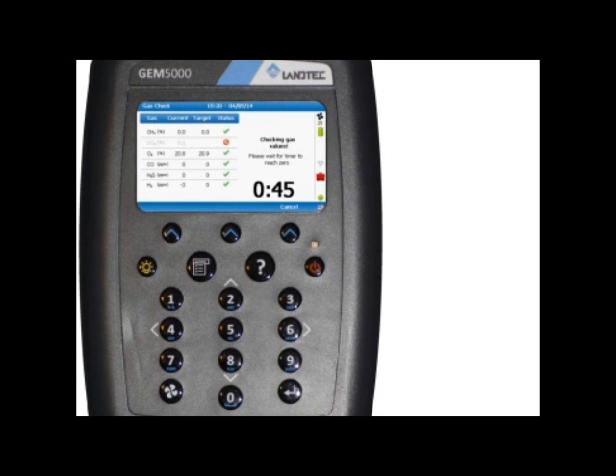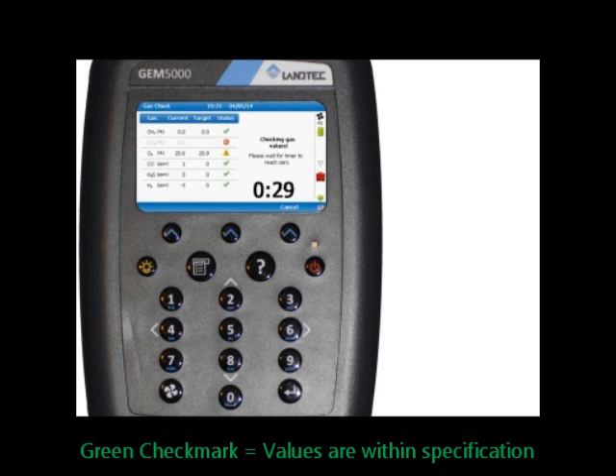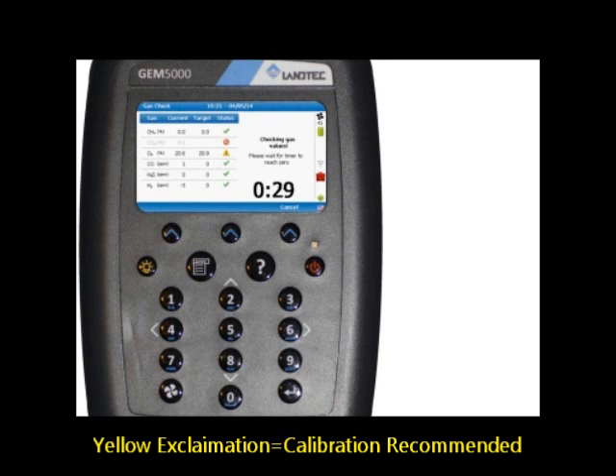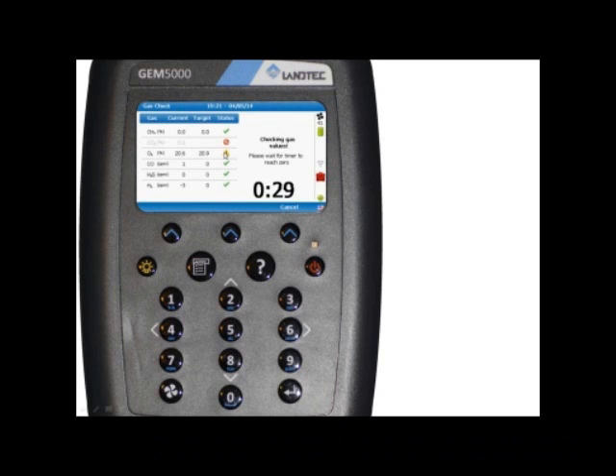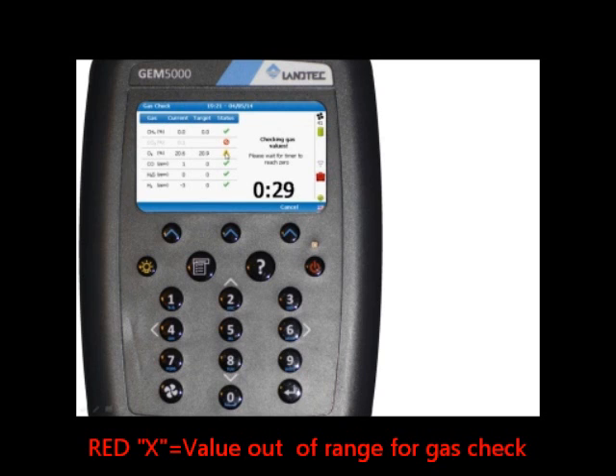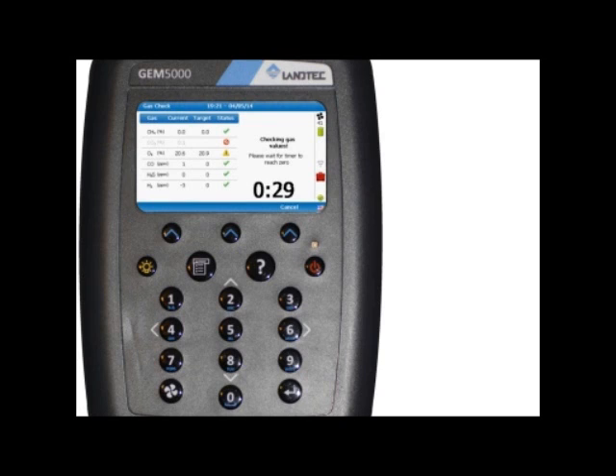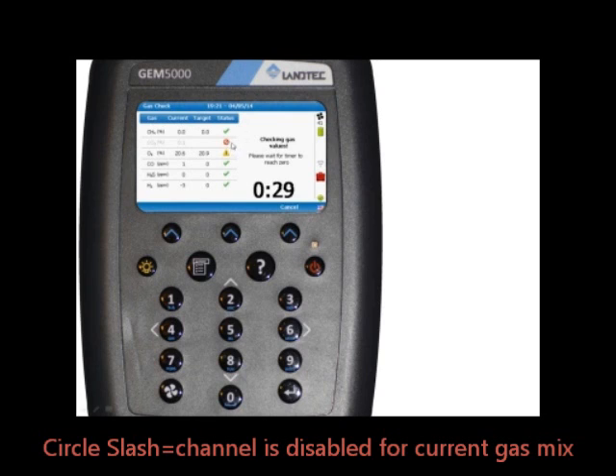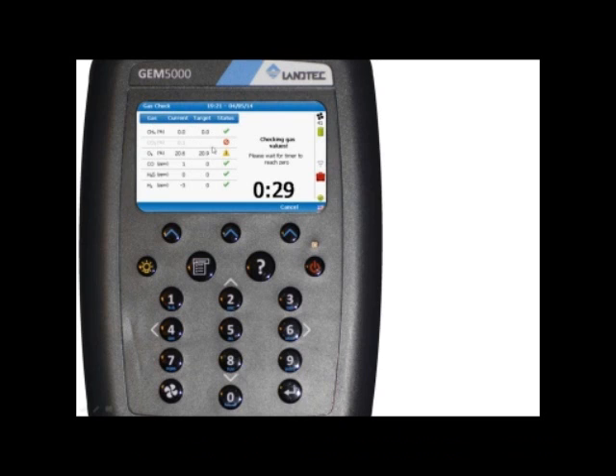Note that during this stabilization period, the current column is going to show the live readings. The target column shows the values we're calibrating to, and under the status column you may see several symbols that might be changing during this period. A green check mark means that the current value is within specification. A yellow exclamation symbol means that the values are close to the target gas, but a calibration is really recommended at this point. A red X means that the current value is out of range and it will fail the check or calibration. And lastly, a circle means that the specific channel is disabled. In this case, the only channel that's disabled is the CO2, as you can see.